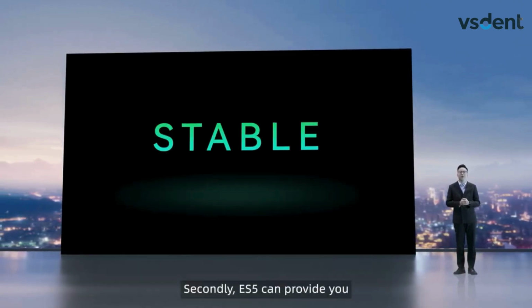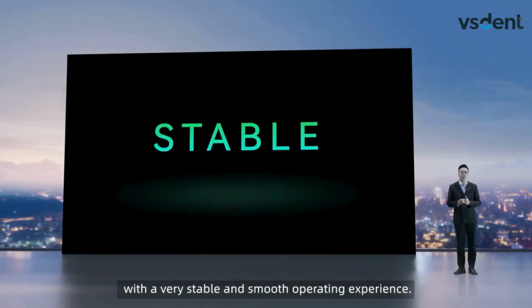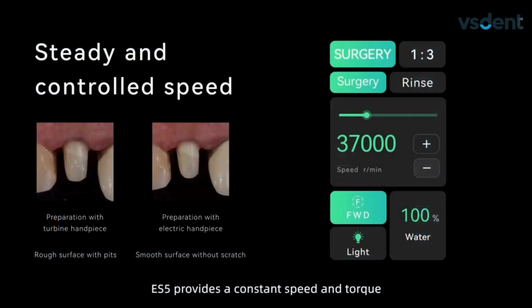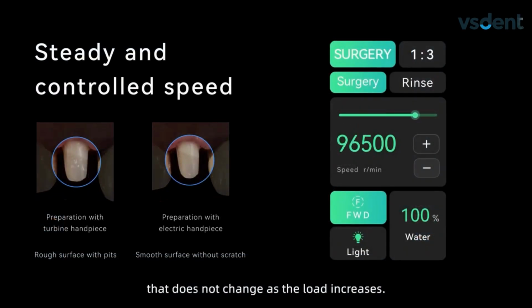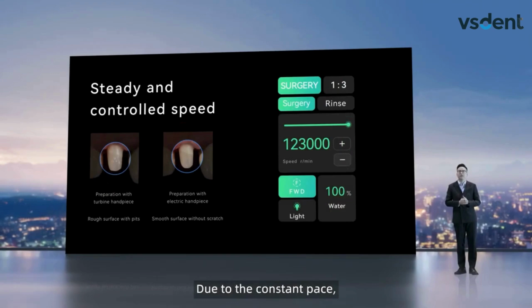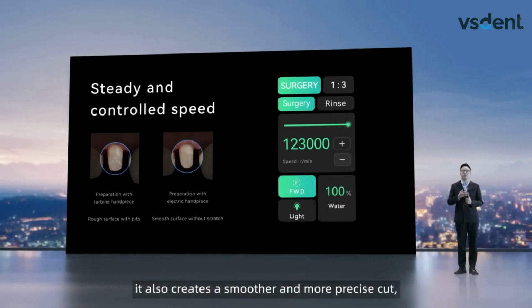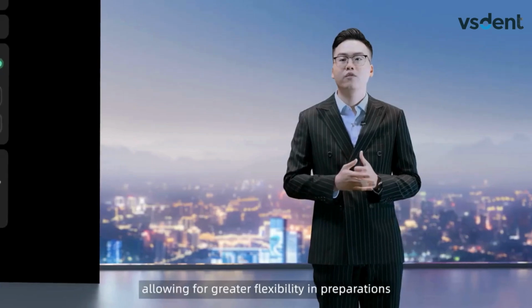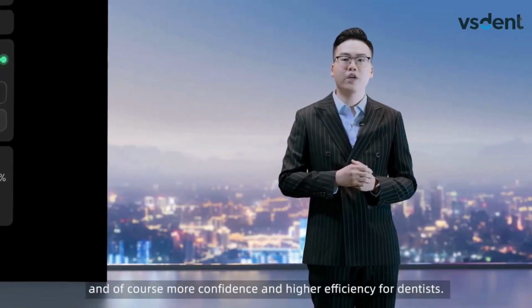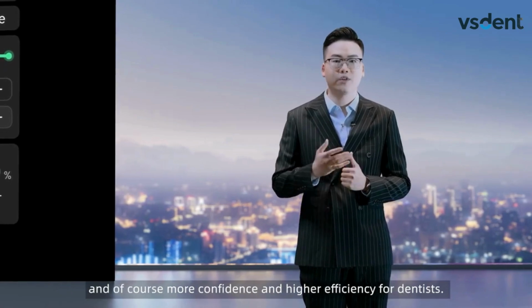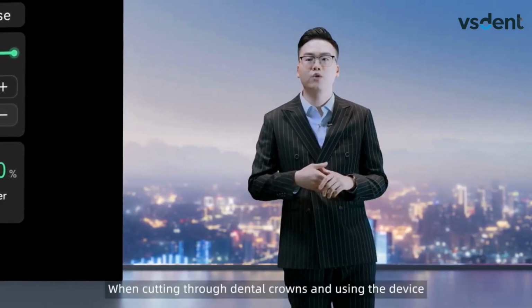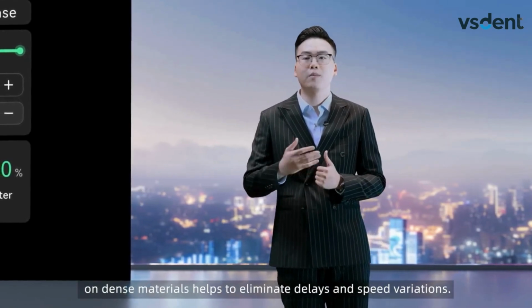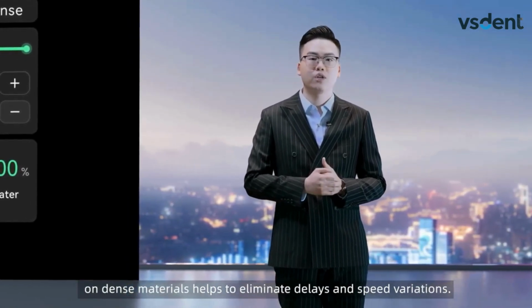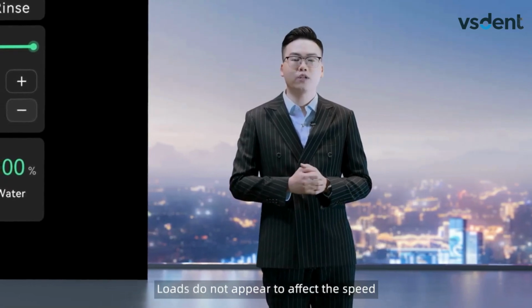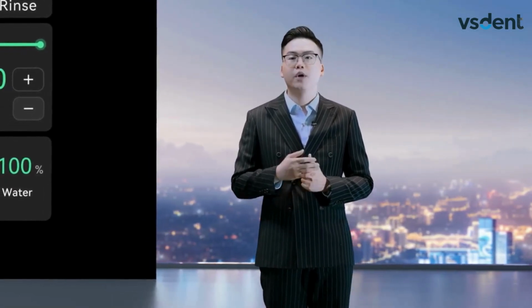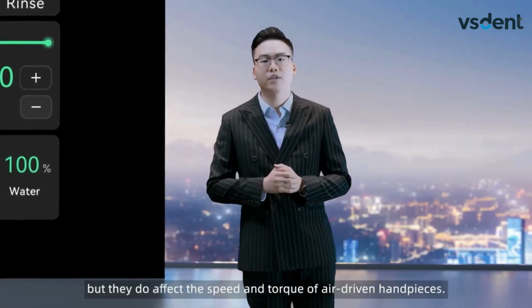Secondly, ES5 can provide you with a very stable and smooth operating experience. ES5 provides a constant speed and torque that does not change as the load increases. Due to the constant pace, it also creates a smoother and more precise cut, allowing for greater flexibility in preparations and, of course, more confidence and higher efficiency for dentists. When cutting through dental crowns and using the device on dense materials, it helps to eliminate delays and speed variations. Loads do not appear to affect the speed and torque of the electric dental handpiece, but they do affect the speed and torque of air-driven handpieces.